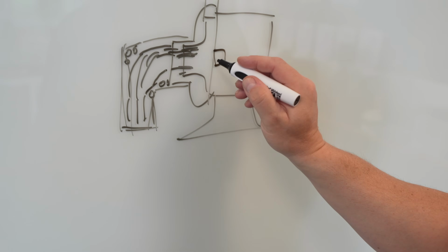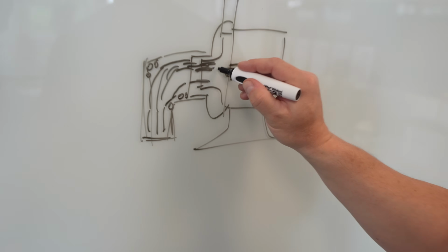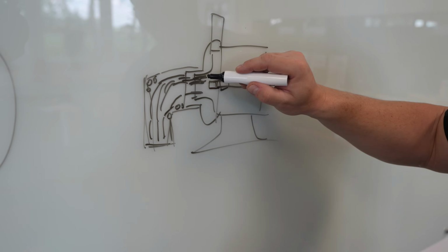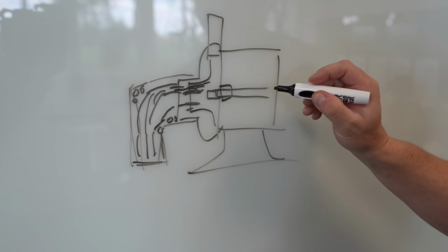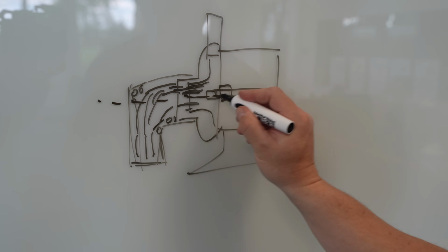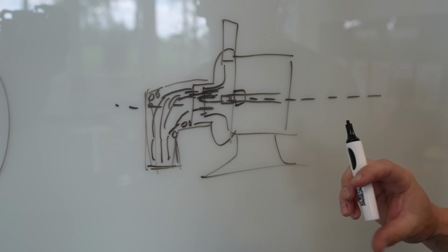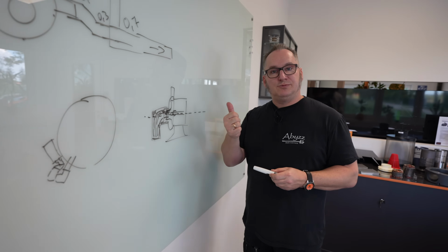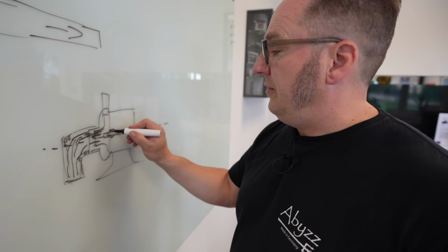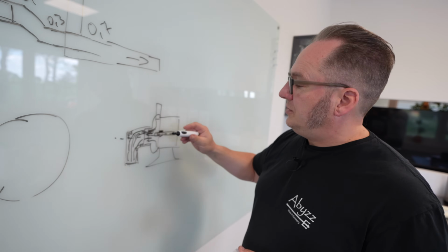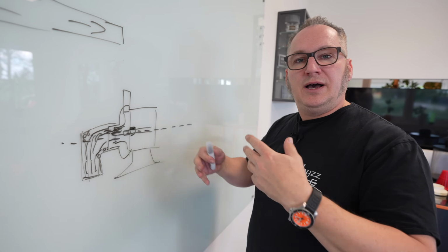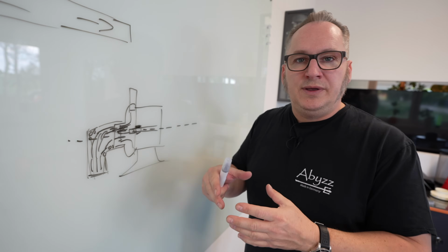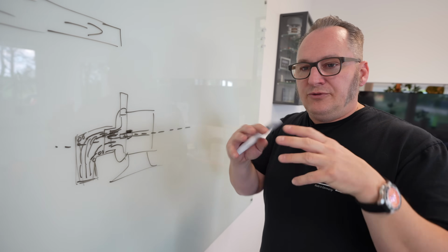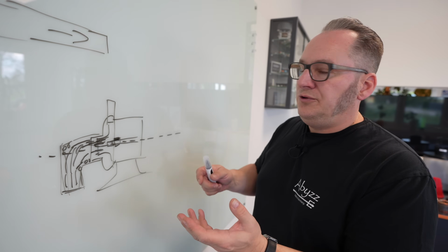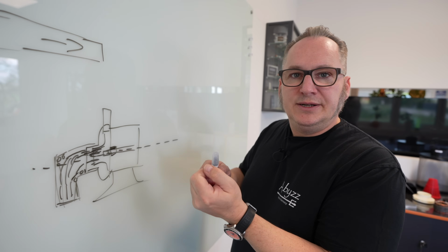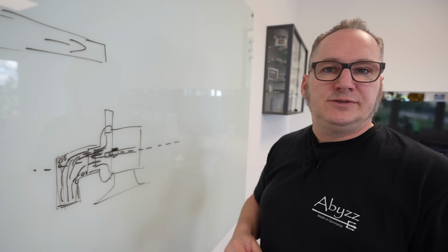There's a bearing in the pump, and then there's a shaft in the pump here. So you actually have more mechanical force on the upper half of the impeller wheel, which, if we put this line in here, creates a force that tilts the impeller wheel, and that reduces your efficiency. That's one part. It also makes sure that you have more wear on the upper half of your bearing on this side, because the shaft is continuously bent to the top. We're using a hydrodynamic bearing, so in general, in between the bearing materials, there's always a fluid film of water. If you push that to one side by pressuring it, you will just have more wear on the bearings, so your bearings just won't last as long.